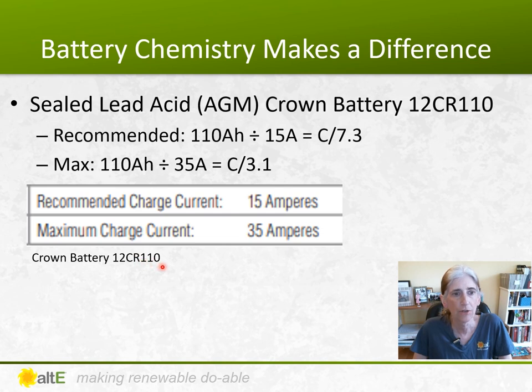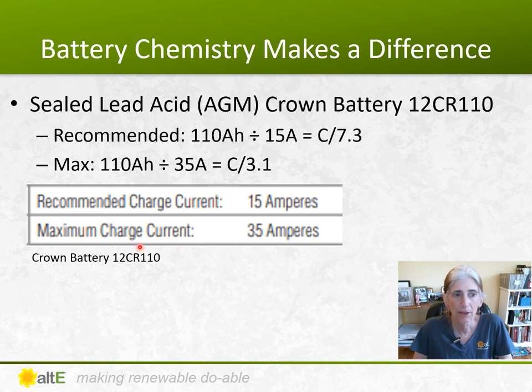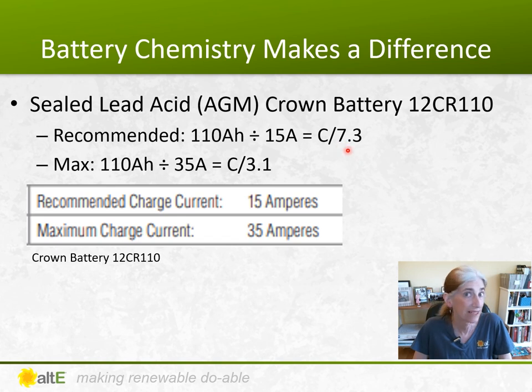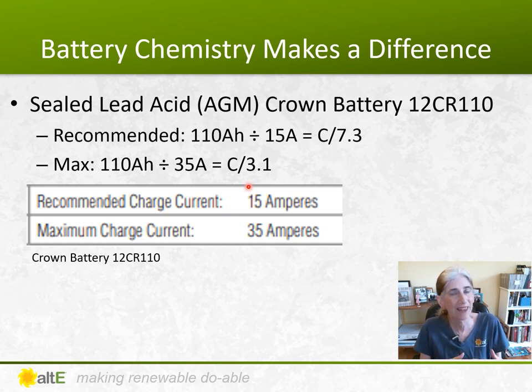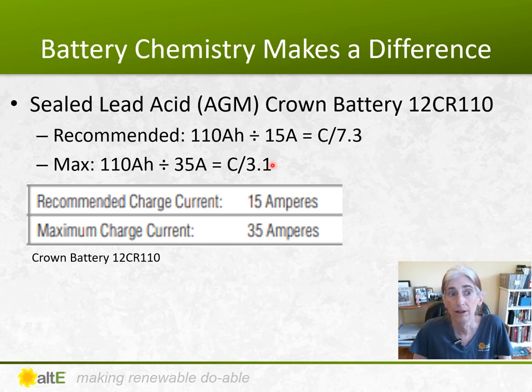Looking at a different brand and type — a sealed lead acid battery from Crown — they list both a maximum and a recommended rate. The maximum is 35 amps, but the recommended is less than half of that at 15 amps, around a C/7.3. As a maximum, you can do a C/3.1. When designing a system, you can aim for the recommended rate for the healthiest battery, or push closer to the maximum.